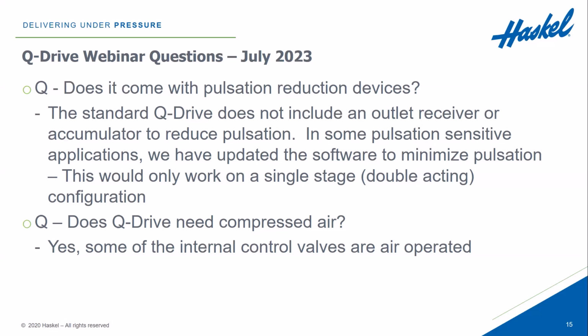That would only work on a single stage double acting unit. You wouldn't be able to do that with a two-stage unit, since you only have gas coming out when the motor goes in one direction. On a two-stage unit, if you had concerns about pulsation, you would definitely want to use some type of a receiver on the outlet to absorb that pulsation.